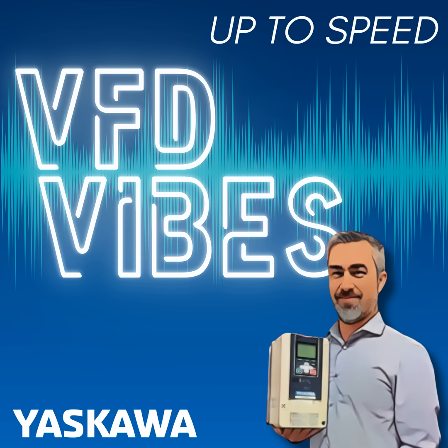Well, there's a couple of ways we can go. First would be what we call an active front-end drive. So I talked earlier, and I think, Greg, you've done some other podcasts on how a drive works, where your AC voltage is converted to a DC voltage in the DC bus, and then that DC voltage is inverted to an output to the motor using IGBTs. So a traditional drive has diodes on the front end, IGBTs on the output side. An active front-end drive has IGBTs on the input side as well as the output side. So the front end has IGBTs, the output section has IGBTs.